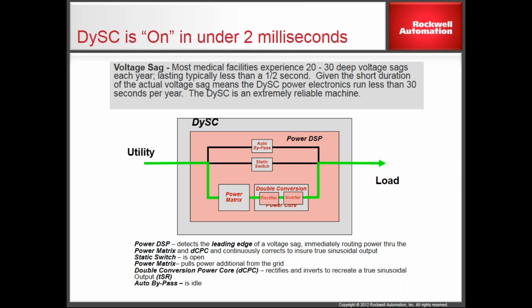Now the thing that makes this all work is it accomplishes this in less than 2 milliseconds from the start of the event. Okay? So it's fast enough to get ahead of any reaction. It's 3 times faster than anything else. The IP in this product is all around this switching. Right? And when I switch, what I'm able to do is pull current from wherever I have it to prop up voltage wherever I need it. So in that same 2 milliseconds, let's say phase 1 drops to 0 volts. I'm going to double the current on phase 2 and prop up the voltage on phase 1 using the energy I just stole from phase 2. So I can steal from Peter to pay Paul.